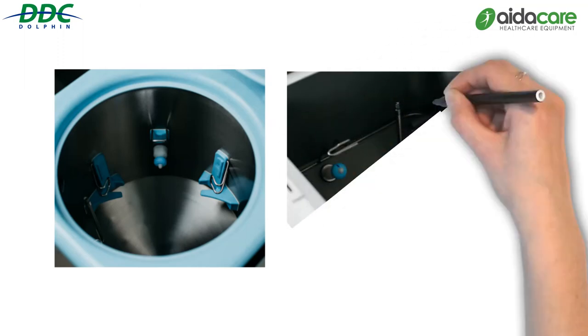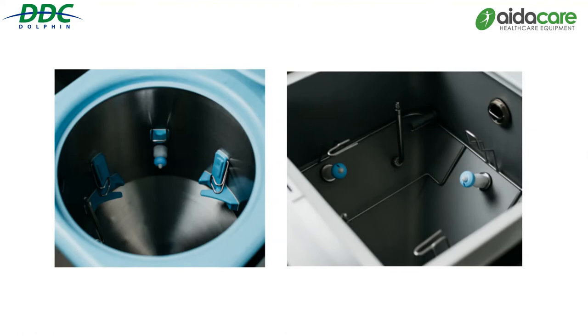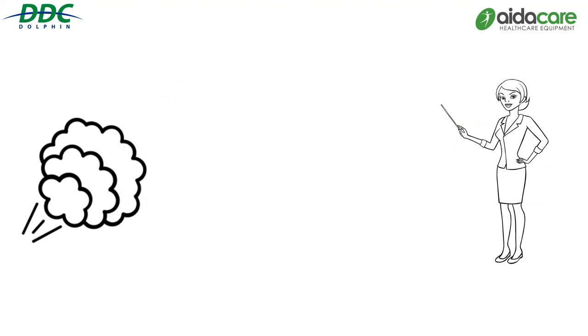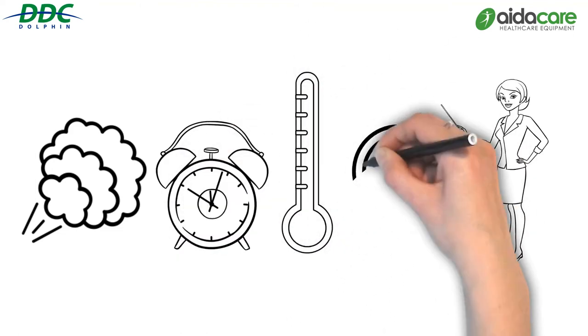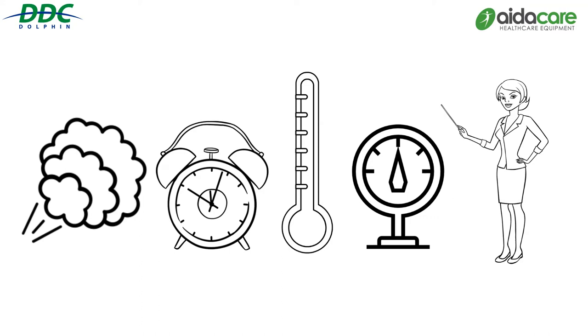The processing of utensils in a washer sanitizer includes two stages. The first is cleaning: fixed and rotated wash nozzles maximise dispersion of waste while minimising water wastage, and steady flow water removes waste and prevents blockages and residue buildup. The second is microbial denaturing using moist heat thermal disinfection. The utensils are fully sanitized to the A0 requirement of ISO 15883 for disinfection, giving peace of mind for the quality of the disinfection process.